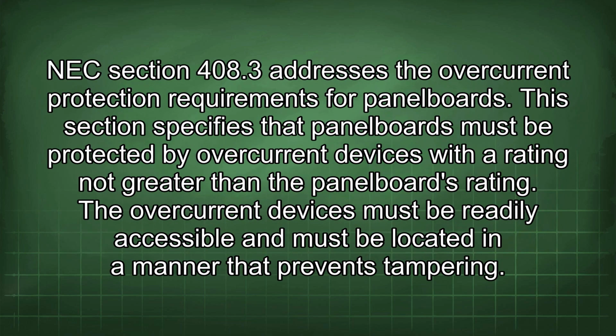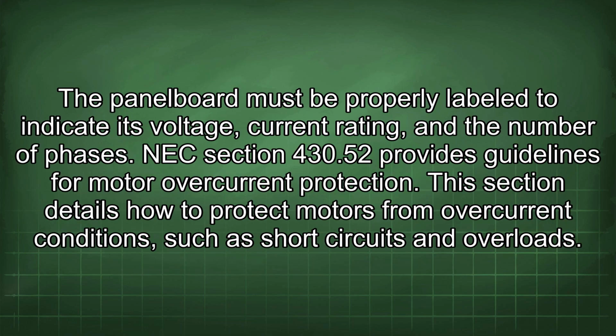NEC Section 408.3 addresses the overcurrent protection requirements for panel boards. This section specifies that panel boards must be protected by overcurrent devices with a rating not greater than the panel board's rating. The overcurrent devices must be readily accessible and must be located in a manner that prevents tampering. The panel board must be properly labeled to indicate its voltage, current rating, and the number of phases.